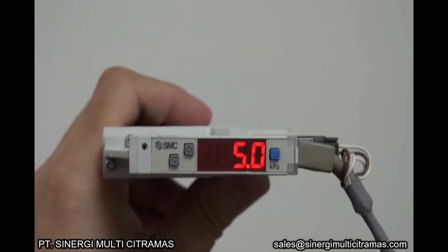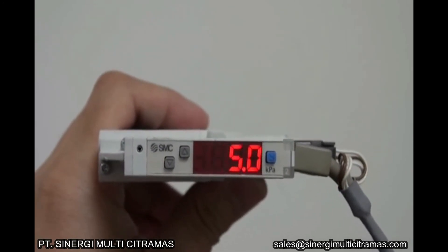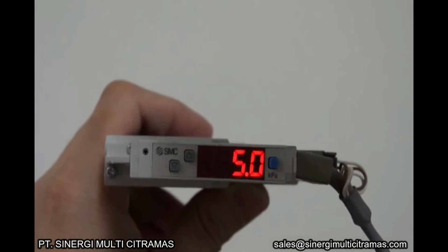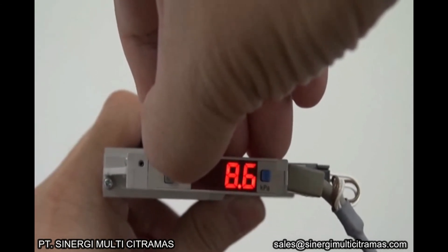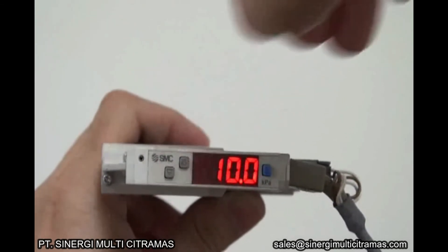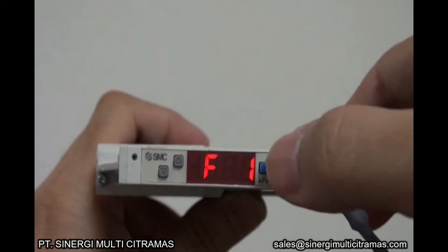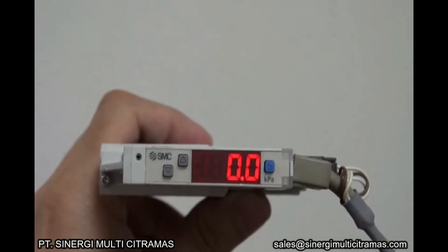The fourth step is to set the hysteresis value to 10 kPa. Press the S button to increase the value. Press the S button to save it. Press the S button for 2 seconds or more to return to measurement mode. This completes the setting of output switch 1.